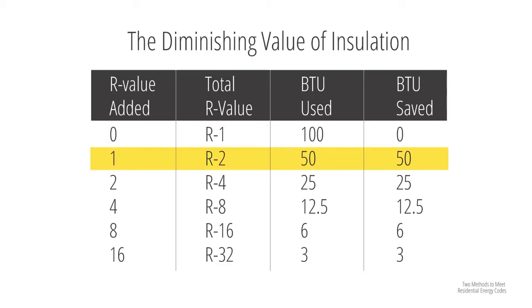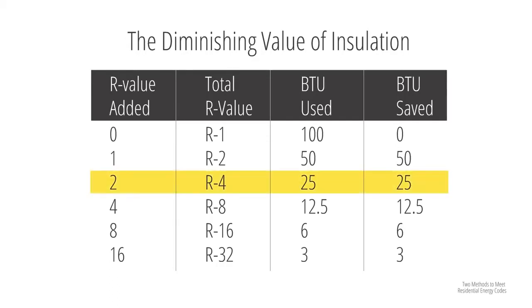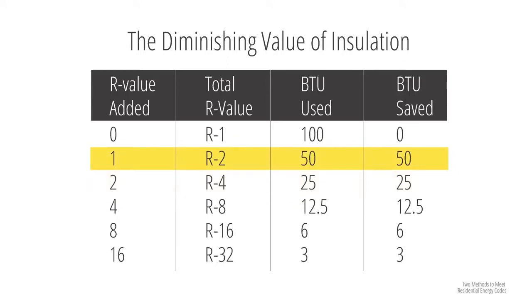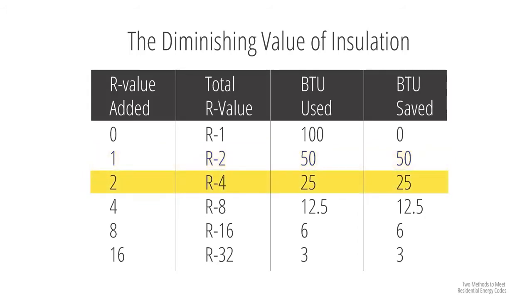In the second row, we add R1, which doubles our system R value to R2. Since we doubled our R value from R1 to R2, we cut our energy loss in half — from 100 to 50 BTUs, saving 50. Now we want to save more energy, so we double the R value again from R2 to R4, adding two more R. This cuts our current energy use in half: from 50 to 25 BTUs, saving 25. Notice — adding our first R saved 50 BTUs, but adding two more only saved 25 BTUs, or 12.5 per R.